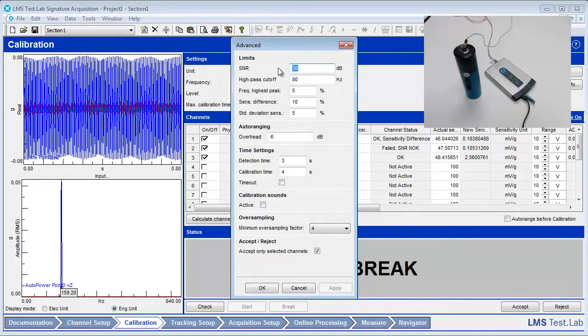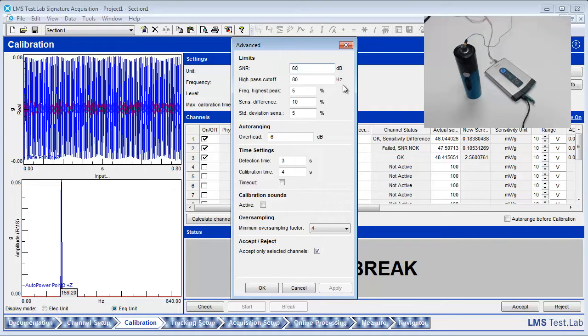By setting the signal-to-noise ratio parameter higher, the off-direction channels will not be calibrated. Change the SNR level to a higher value like 60 dB. By setting the SNR higher, the false calibration trigger caused by crosstalk is eliminated.